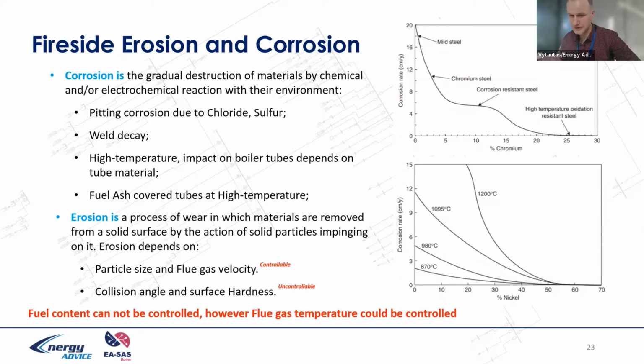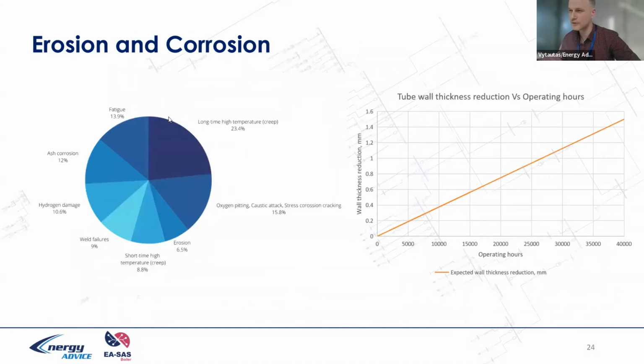So if you have a very good recirculation flow, which is hard to control with only pressure, as we can see from previous slides, and collision angle and surface hardness. Probably we cannot control the collision angle, but particle size and flue gas velocity we can control through the tubes. So in fact, most effects I have ever seen are erosion, and erosion is related to automation level. If the automation level is poor, we have problems. Corrosion is happening, but not so often. There is, of course, a distribution from book knowledge about erosion and corrosion and what the split between them could be, but in my experience, erosion is the more common effect instead of corrosion.